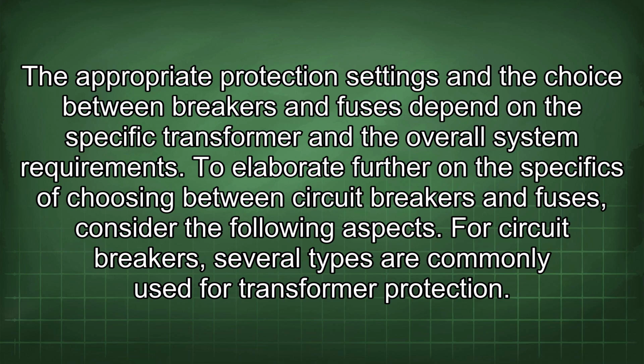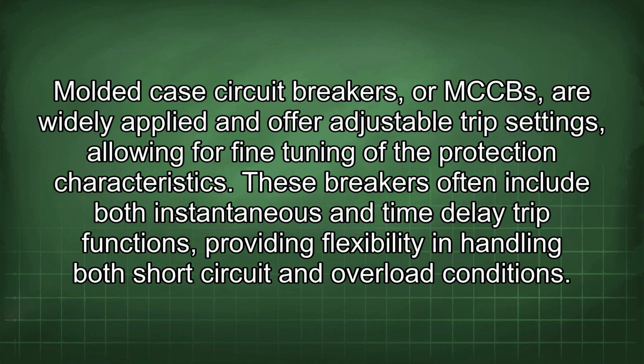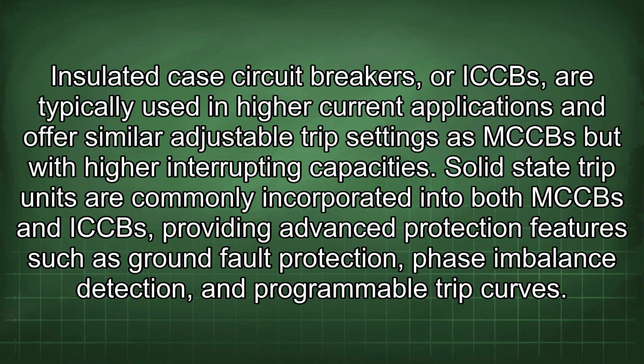For circuit breakers, several types are commonly used for transformer protection. Molded case circuit breakers, or MCCBs, are widely applied and offer adjustable trip settings, allowing for fine-tuning of the protection characteristics. These breakers often include both instantaneous and time delay trip functions, providing flexibility in handling both short circuit and overload conditions. Insulated case circuit breakers, or ICBs, are typically used in high current applications and offer similar adjustable trip settings as MCCBs but with higher interrupting capacities.